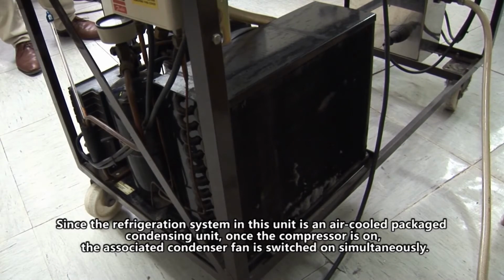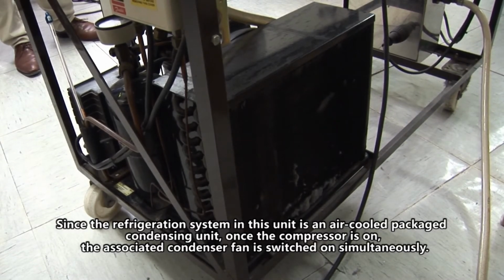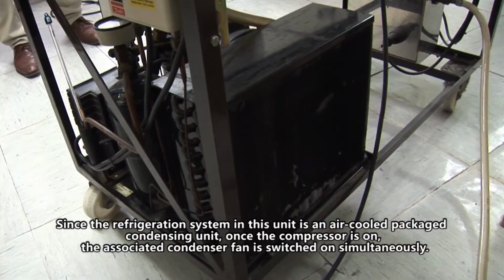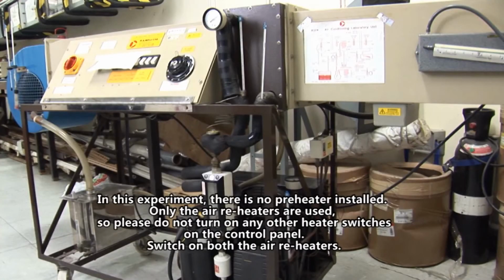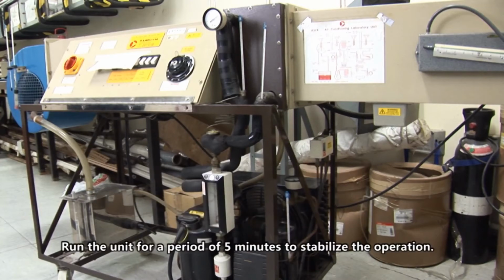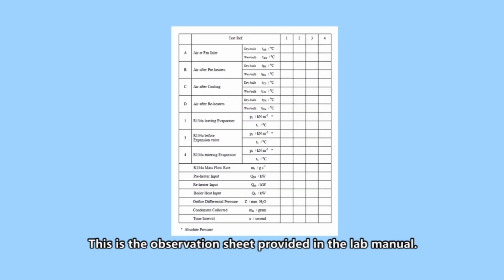Since the refrigeration system in this unit is an air-cooled package condensing unit, once the compressor is on, the associated condenser fan is switched on simultaneously. In this experiment, there is no preheater installed. Only the air reheaters are used, so please do not turn on any other heater switches on the control panel. Switch on both the air reheaters. Run the unit for a period of 5 minutes to stabilize the operation.